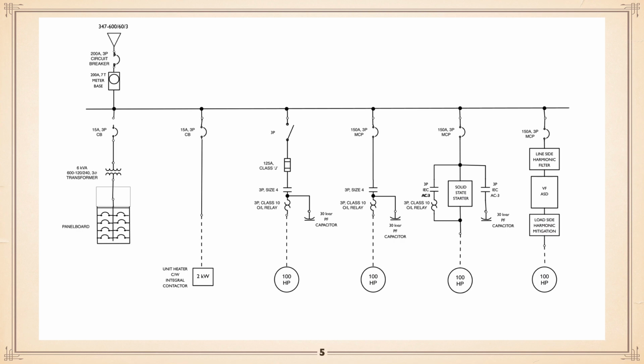So all you need is, if you're at this kind of lower voltage, you really don't have to worry so much about load side protection. Line side, if it's more than 20%, probably at the lower voltage, not such a big deal. Certainly at 600 volt, yes, these line and load side filters.